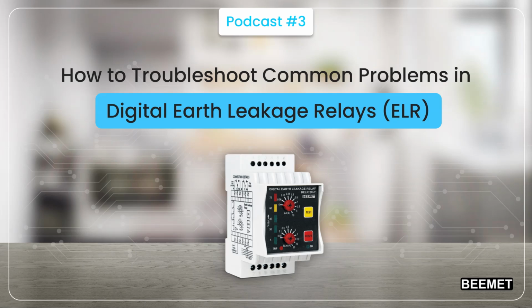Understanding Digital Earth Leakage Relay components. An ELR is a device that checks the flow of electricity through a sense core, CBCT, to make sure it is balanced. It sends a signal to the breaker to trip when the balance is lost. This prevents digital ELR faults from harming equipment or people. A basic system includes a microprocessor that analyzes current, a display that shows readings and relay status, a CBCT sensor that detects leakage, relay outputs and test functions that trigger tripping.